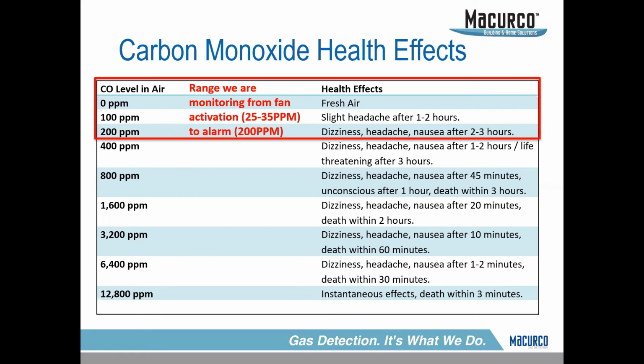So what we do is take the low end of that threshold, an OSHA standard, and say at 200 ppm we're going to full-blown alarm. You might get a headache, dizziness, or nausea after a couple hours, but we're already activated within a second of that hitting 200. So your fire department is being called and your evacuation protocols are in place. We like to have a low-level threshold because we can do a valve closure or a fan/ventilation activation point. That's the reason for the low-level and high-level differentiation.